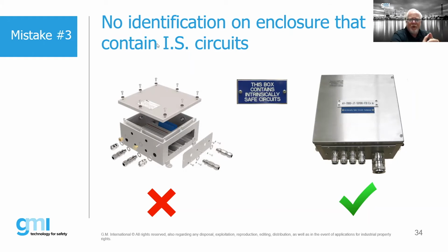One of the other issues is that it is a requirement basically worldwide that an enclosure containing intrinsically safe circuits be labeled as such. This is one of the things that I see quite a bit, that we'll see a panel or an enclosure that is basically without that marking. We want to see a marking that says that this enclosure contains intrinsically safe circuits. On the left-hand side, we see a junction box with some blue terminals in there. Those blue terminals are typically used for intrinsically safe circuits from a visual standpoint, but the enclosure itself does not have a label. The enclosure on the right does. That's what we want to see when we're looking at enclosures that contain intrinsically safe circuits.